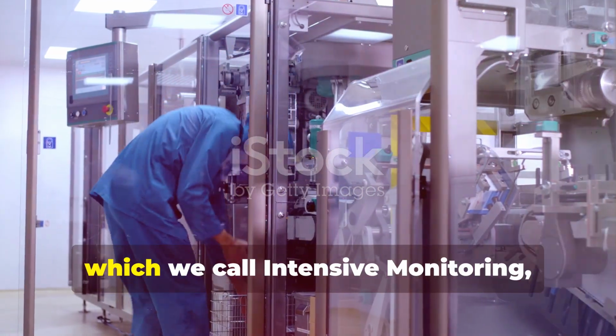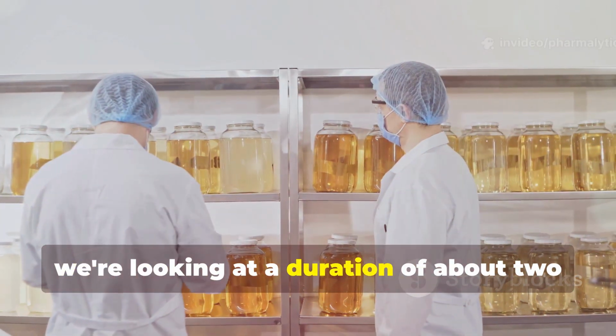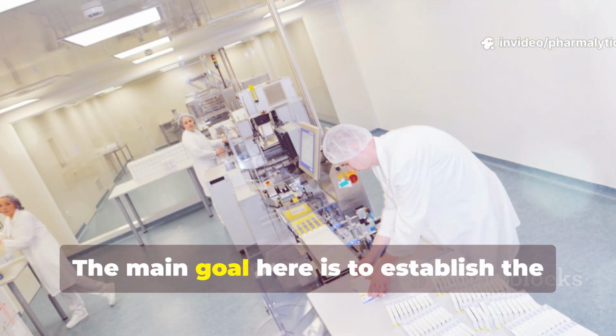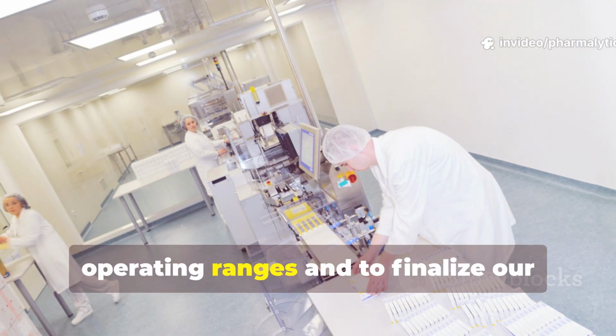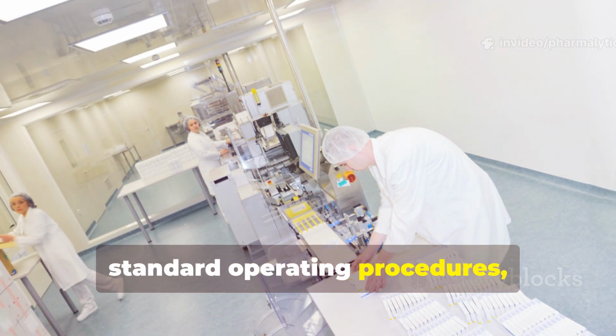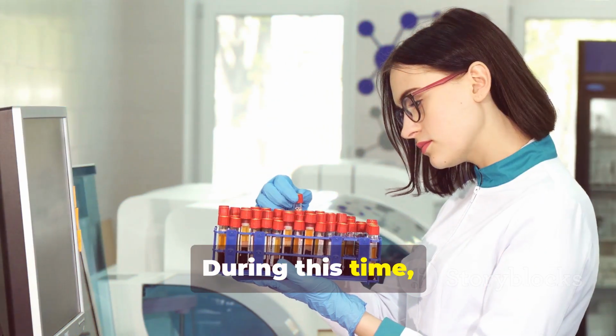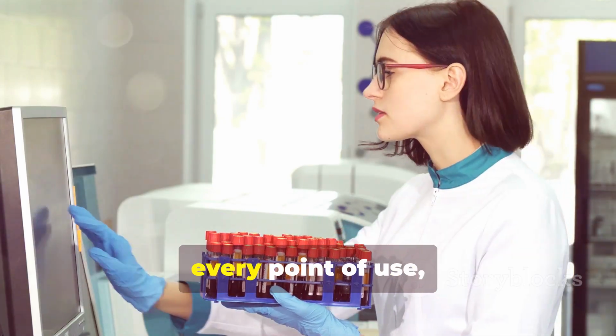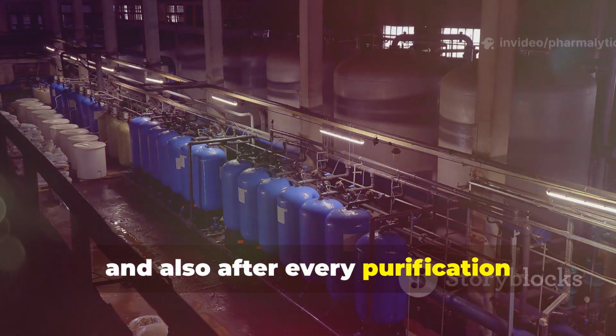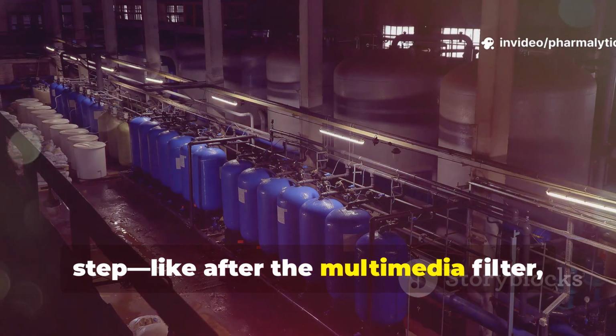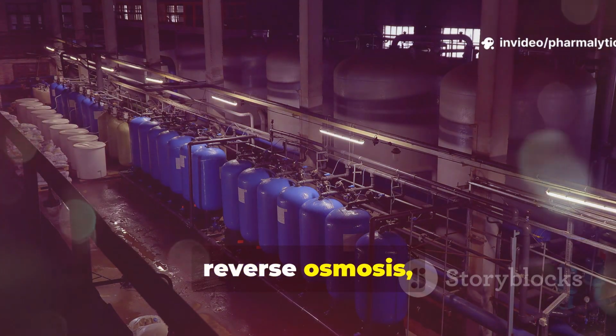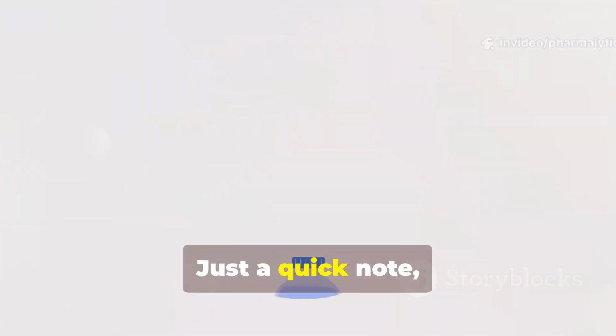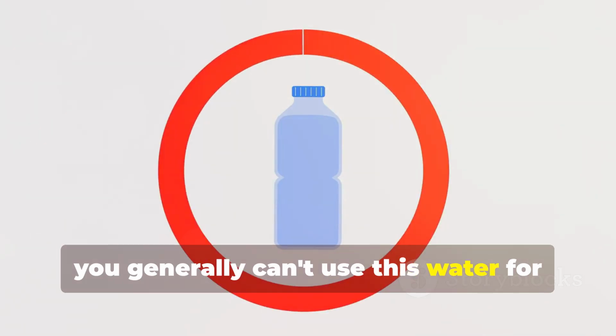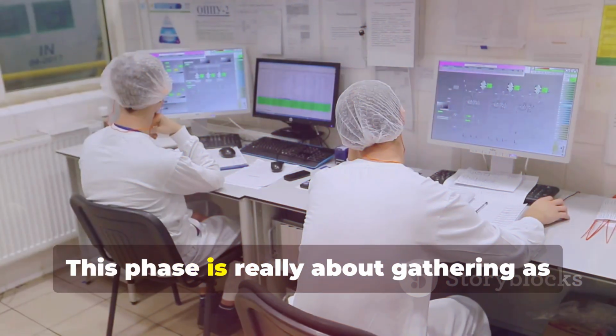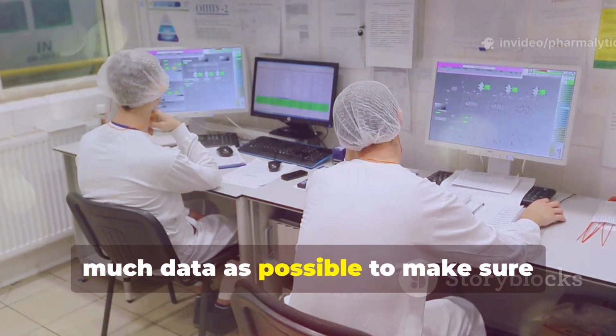Alright, so in this phase, which we call intensive monitoring, we're looking at a duration of about 2 to 4 weeks. The main goal here is to establish the operating ranges and to finalize our standard operating procedures, or SOPs. During this time, sampling is done every single day from every point of use, and also after every purification step, like after the multimedia filter, the softener, reverse osmosis, and the EDI. Just a quick note, you generally can't use this water for commercial production yet. This phase is really about gathering as much data as possible to make sure everything's running smoothly.